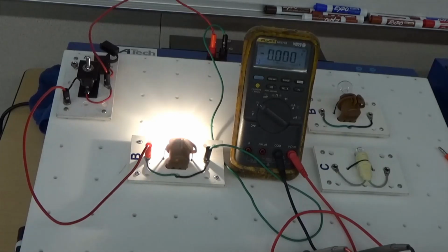If I'm doing a voltage drop somewhere in my circuit, and I see an unexpected voltage, I know I have a fault there. Chiefly, I find an unwanted resistance. And you say, hey, Mr. Linares, I thought we were looking for voltage, not resistance. Well, we have to remember something very, very carefully here. Resistance consumes voltage. So if I find an unwanted voltage drop, I also find an unwanted point of resistance.